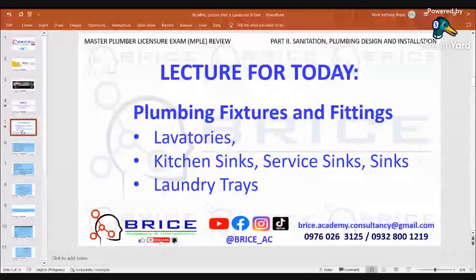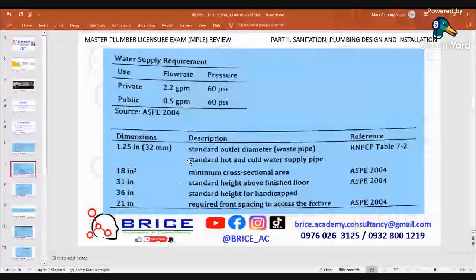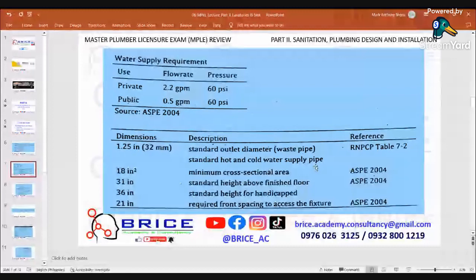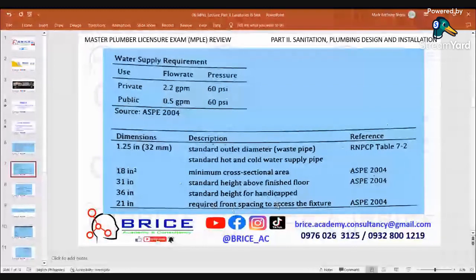For dimensions: 1.25 inches or 32 millimeters is the outlet diameter of the waste pipe. Standard hot and cold water supply reference is RNPCP Table 7-2, with 18 inches square minimum cross-sectional area. Standard height above finished floor is 31 inches. For handicap, 36 inches, with 21 inches required front spacing to access the fixture. Source: ASPE 2004.